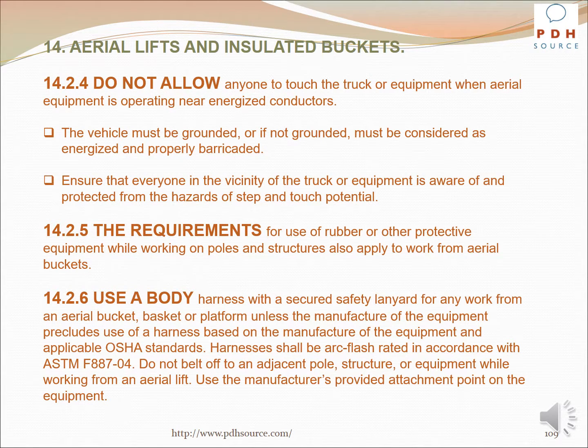Do not allow anyone to touch the truck or equipment when aerial equipment is operating near energized conductors. The vehicle must be grounded, or if not grounded, must be considered as energized and properly barricaded. Ensure that everyone in the vicinity of the truck or equipment is aware of and protected from the hazards of step and touch potential. The requirements for use of rubber or other protective equipment while working on poles and structures also apply to work from aerial buckets.